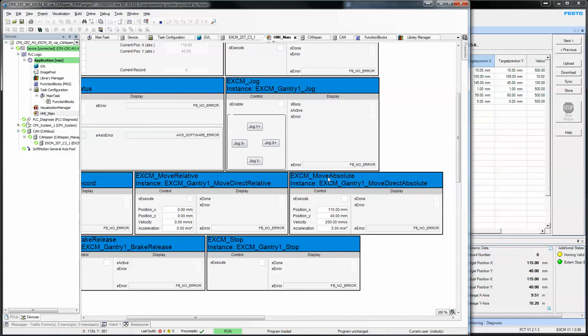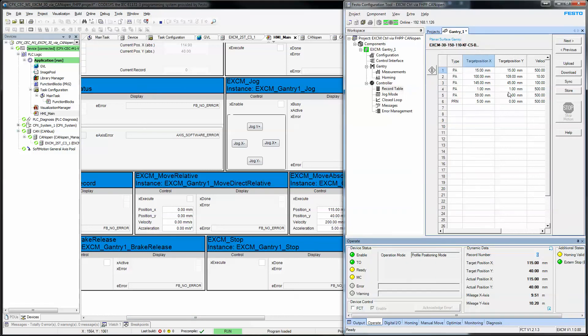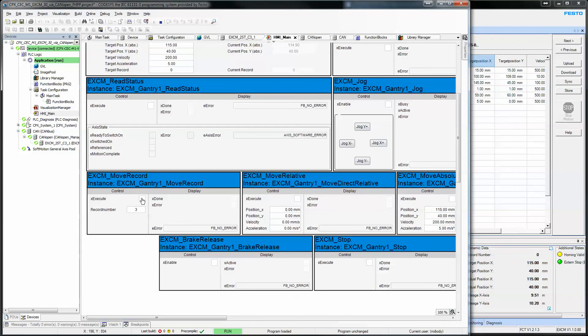So, this move absolute, that's basically using direct mode. So, there's your flexibility. So, you can either use, you know, direct mode moves for all your various moves, and you can have the PLC write values to the table before you execute each move. Or, you can populate the tables in this record table right here in FCT, and you can have them individually executed by this function block right here.